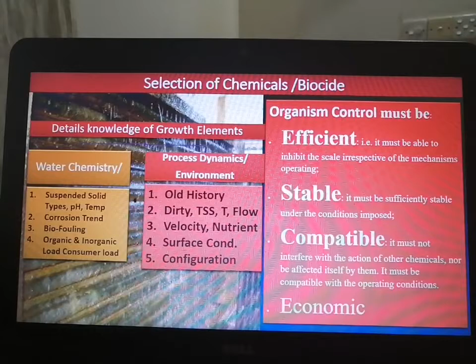So if you want to select any biocide, we definitely have to consider water chemistry, different organisms, fouling chance, as well as environmental aspects. The chemistry we select must be efficient across different spectrums. It must be stable with other environmental factors like temperature and pH. It must be compatible with other chemicals, because all the time we have to use multiple chemicals, and it must be economical.